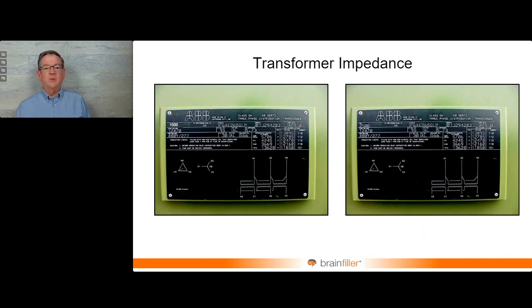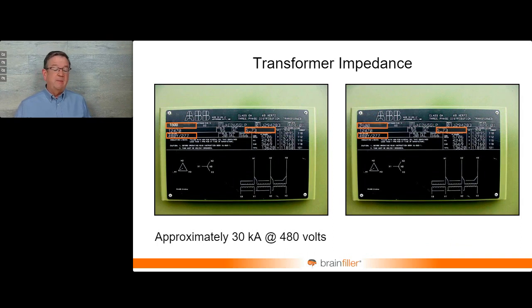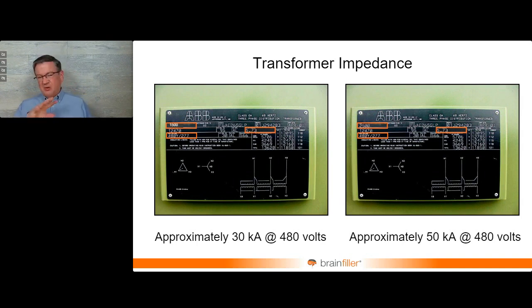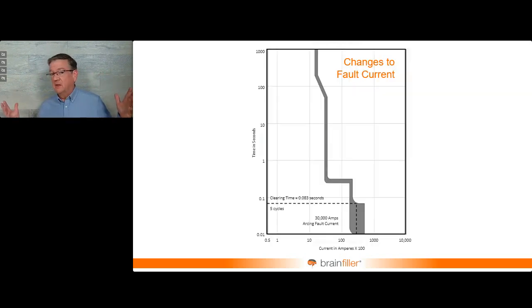As far as transformers, transformer size has a lot to do with this, and transformer impedance. So if you have the same impedance like I'm showing here, but different sizes, it affects the short circuit current. The 1500 kVA on the left, typical short circuit current would be around 30,000 amps. The one on the right, take it up to a 2500 kVA, short circuit current goes up to approximately 50,000 amps. That could have a big impact on the incident energy. It can also have an impact on how a protective device operates.